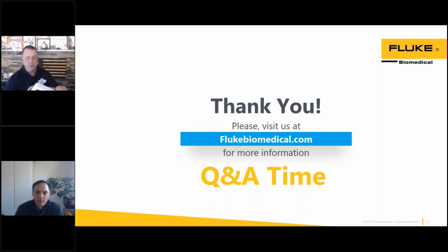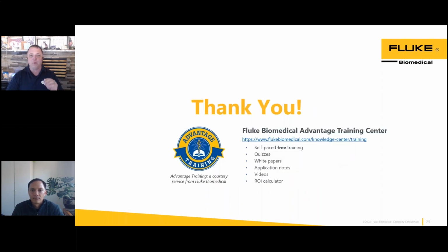Sure can. You sure can. The IDA-6 is capable of reading in both volumetric and gravimetric. So as long as you remember that 1.000 milliliters weighs 1.000 grams of pure water, it's a direct conversion. So you can run one and read the other. And the IDA-6 is capable of flipping back and forth between grams and milliliters. So you can 100% do it with the IDA-6. And in fact, what you might find is you're going to have higher resolution with the IDA-6 than with the scale. A lot of the scales I see read to the hundredth, and the IDA-6 is able to go to the thousandth. So you'll have much more resolution.